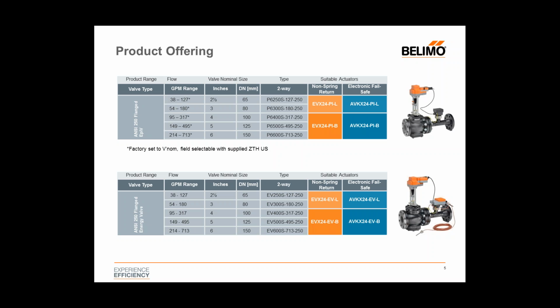But with the energy valve, we have a little bit of increased flexibility for setting the flow due to the high technological ability of this actuator. Once again, we can preset the flow at the factory for the energy valve. So in the case of the 2.5 inch, if they wanted it set all the way down to 38 GPM for some specific reason, that can be done here at the factory. So when it leaves the factory, it's already set when it arrives on the job site. It just shows, once again, the flexibility and the technological advantage of the product lines. So that would cover both the ePIV and the energy valve ANSI 250 version product offerings.